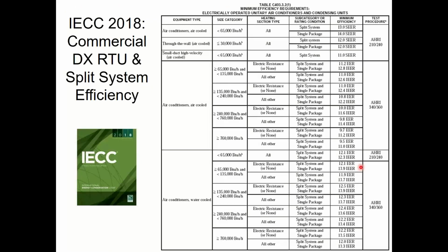When I look at the energy code, which we're required to comply with, obviously, for both new construction as well as replacement units, if I look at the small stuff, 5 tons and less for packaged systems, I need to be 14 SEER. Package meaning like a rooftop. If I have a split system, 2 pieces, 1 indoor, 1 outdoor, I only need to be 13 SEER. But 14 SEER for the packaged systems. If I go to the big stuff, they need to look and see how big is big in this discussion. So 65 to 135,000 BTUs. And then if I have electric heat or all other heat types, all other means gas heat or hydronic heat. If it's a heat pump, there's actually a separate table, which is a separate discussion for another day.